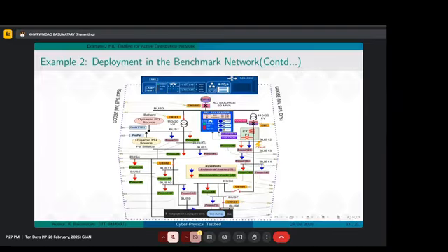That is the network. We have also integrated the SEL-3530 automation controller. The purpose of integrating this RTAC is to monitor the whole distribution system's voltage, current, load profile, active and reactive power, and some distributed energy resources modeled as a dynamic PQ source here, a PV source, and a battery. We take all this data in the RTAC to monitor the actual benchmark distribution system, which is kind of realistic.